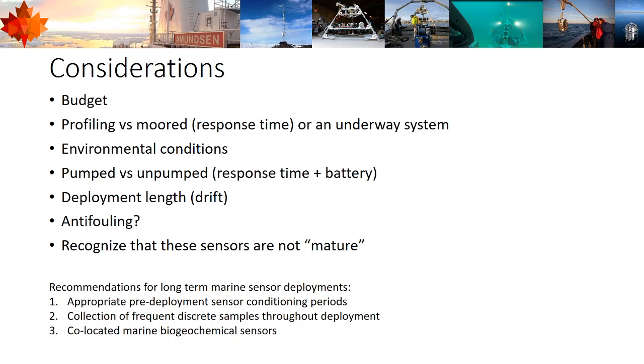Anti-fouling. So if biofouling is a real issue in the region that you're going to be putting these sensors, then anti-fouling measures might be something you want to consider. Talk to the manufacturer, let them know where you're putting it, what you expect, and if biofouling is an issue, there are solutions that can be made.